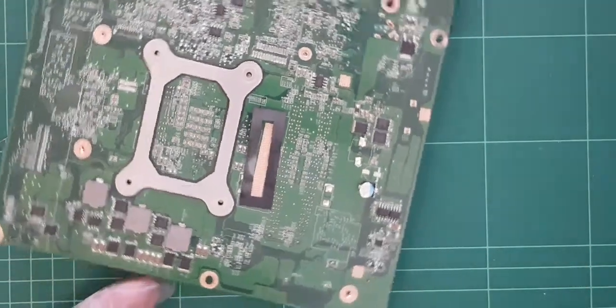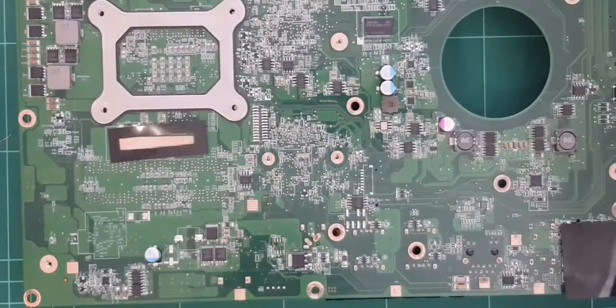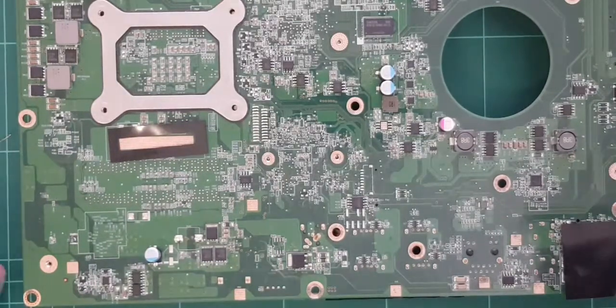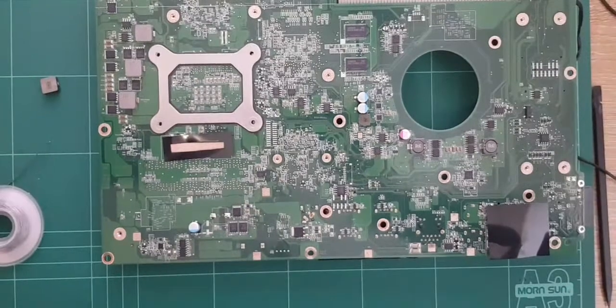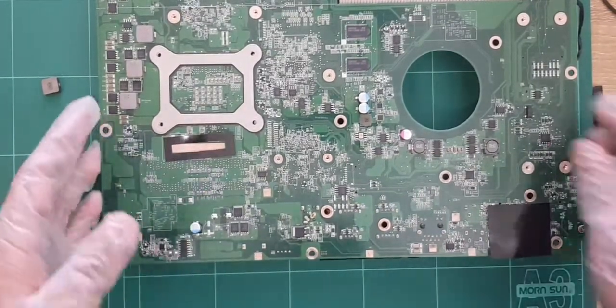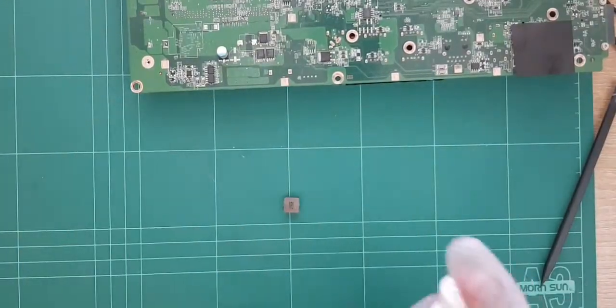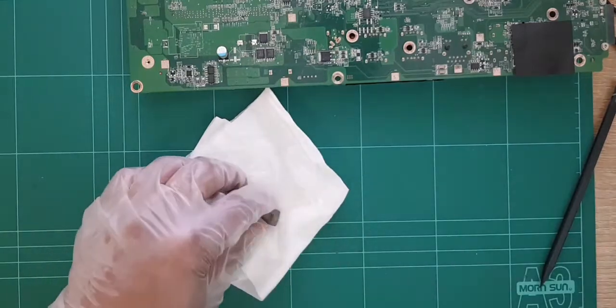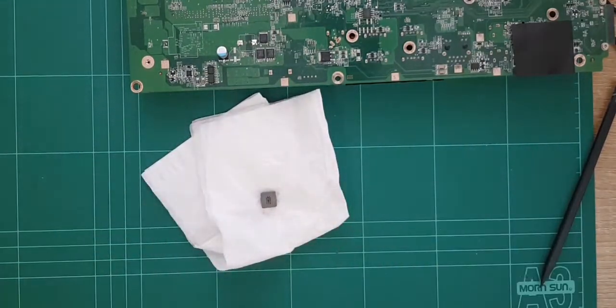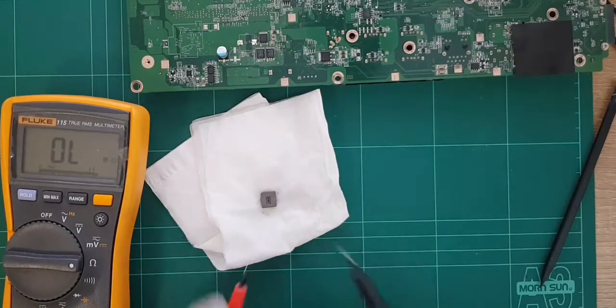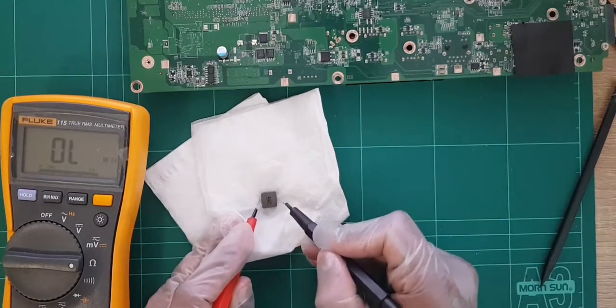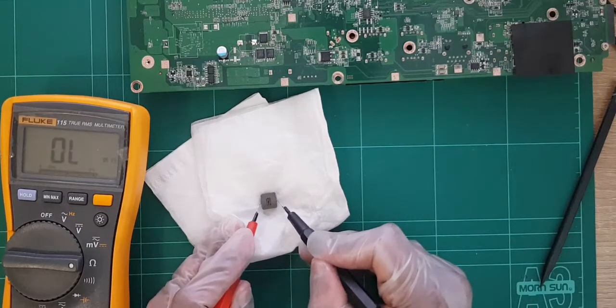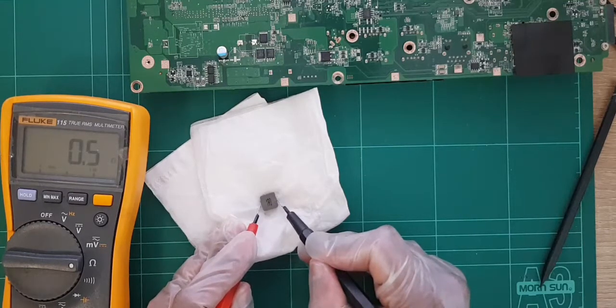Once you remove something out of circuit and it's hot, just let it cool down for a little bit, because if you start taking measurements straight away, that's quite warm, the measurements will not be accurate, because obviously heat increases the resistance. And now I will check this. So let me spray a bit of IPA onto this to cool it down, and I'll show you on resistance mode. This should be reading 1 ohm or close by, and okay, that's reading 0.5, 0.4, so that will need to be replaced. So that's not really reading the best.